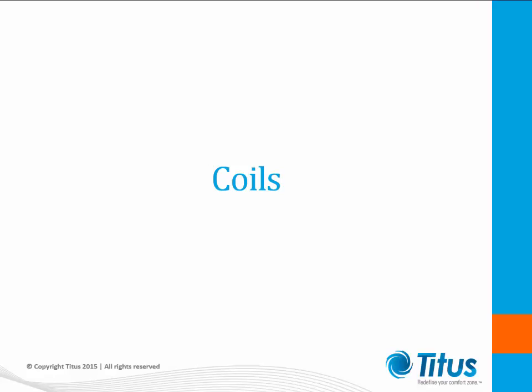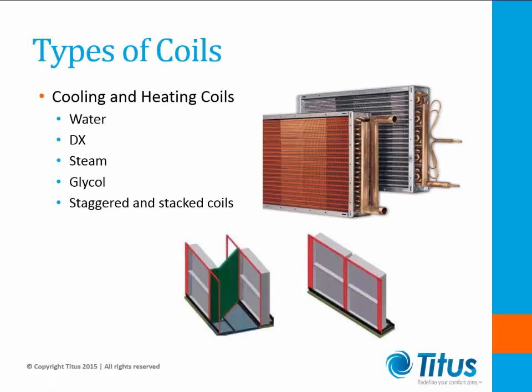Stepping to the next item on our list would be the coils. There are several different types of coils available within the units. Those examples can be water, DX, steam, and even glycol. They may also be found in different mounting configurations such as staggered and stacked coils. Staggered coils allow more surface area for cooling and heating, but warrant longer cabinet segments. Stacked coils are often split to allow flexibility in cleaning and changeout. Depending on the tube diameter used within the coils, typical splits of the coils range between 47 and 50 inches in height.